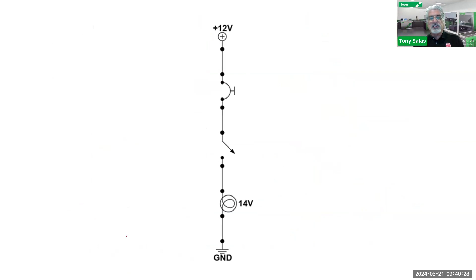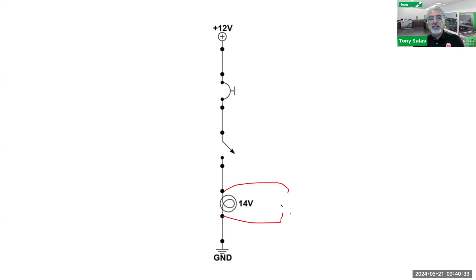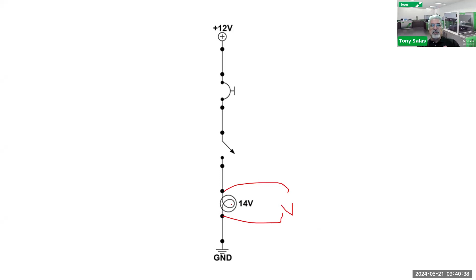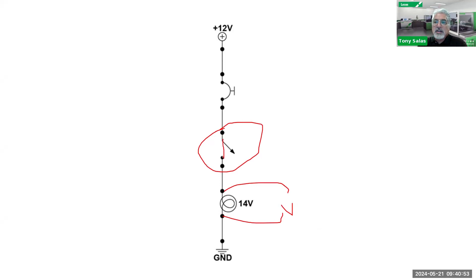So once again here we see the circuit. Will I show voltage drop the way the circuit is illustrated here? If we're taking a test question for certification, should I see voltage across that load? The answer is no. Why? Because the circuit is off. You want that circuit to be on, and that's what you're going to see there. So always remember, anytime you're doing voltage drop testing, the circuit must be on.